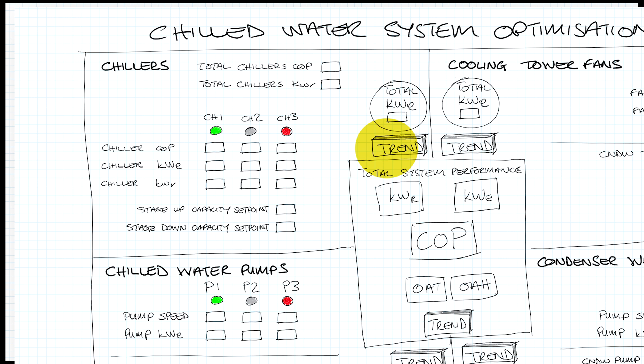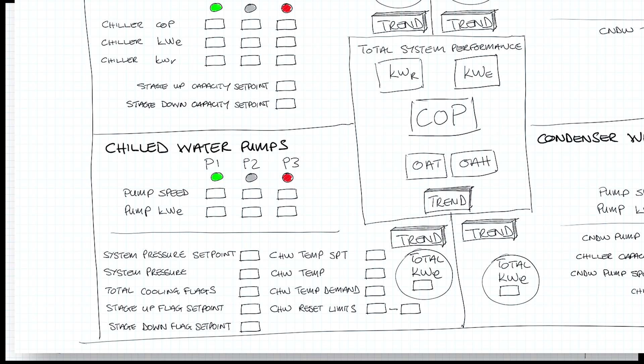There's a trend button - click it and it takes you to a trend of all that information: the COPs, outside air temperature, kilowatts, when you staged up, and so on. In the bottom left I have the chilled water pumps - three pumps, one running - with the speed and kilowatts of electricity for each. Below that I have all the parameters for the system pressure reset, the totalization of the cooling flags, the stage up/stage down flag (similar to ASHRAE 36), and the supply temperature reset strategy, with a trend button showing all of that data.